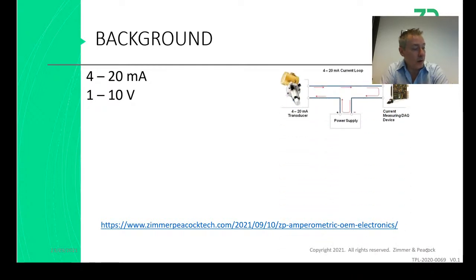But when the inquirer asks, do you have a sensor with an output for 4 to 20 milliamps - in a lot of industrial applications and process control you will have transducers. Transducers, for me, is a broader category, and sensors, including biochemical sensors, are a subset of those. People are interested in sensors that give out a 4 milliamp signal when the analyte is at 0, and a 20 milliamp signal at full-scale deflection, for example when the analyte's at 100%. So this is the background to the question - the person asking clearly has, I wouldn't say an industrial background, but more of an engineering and process background.